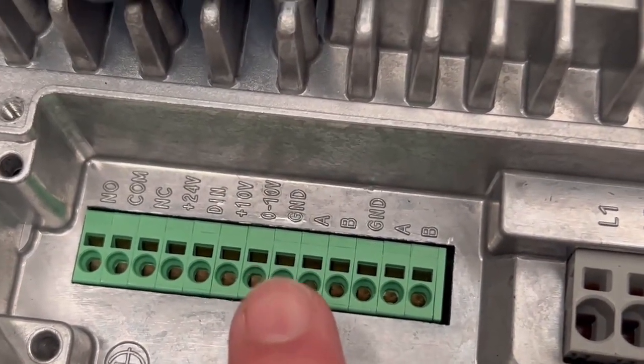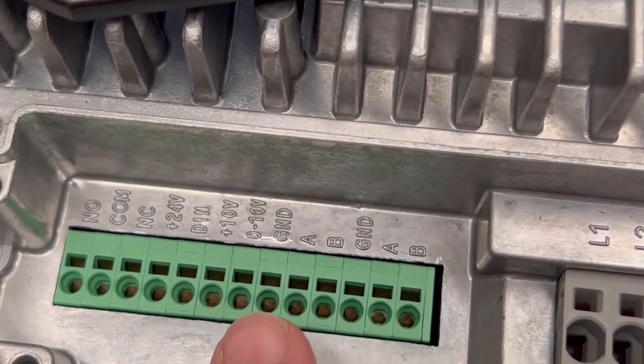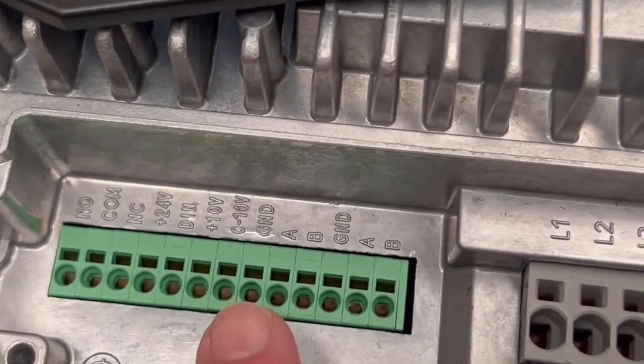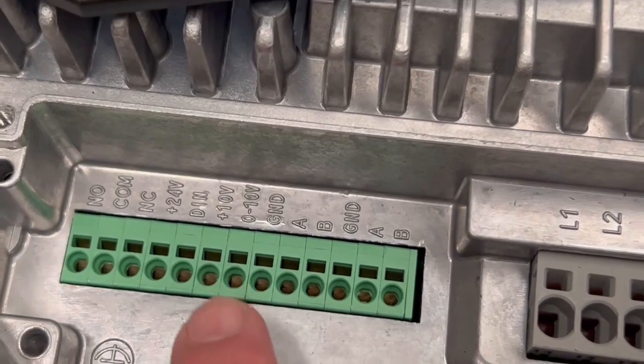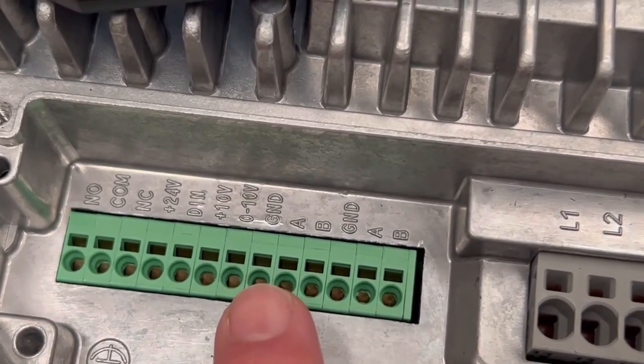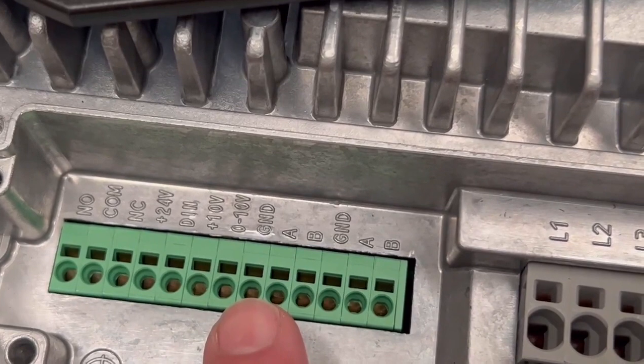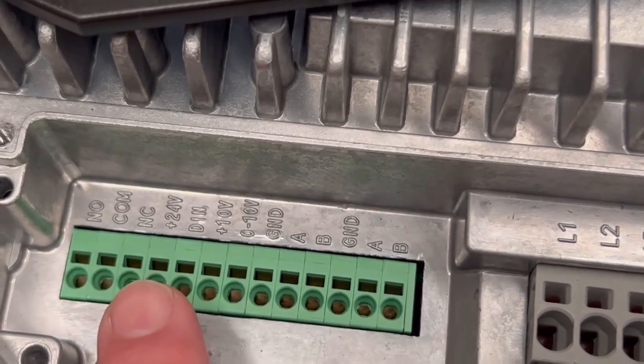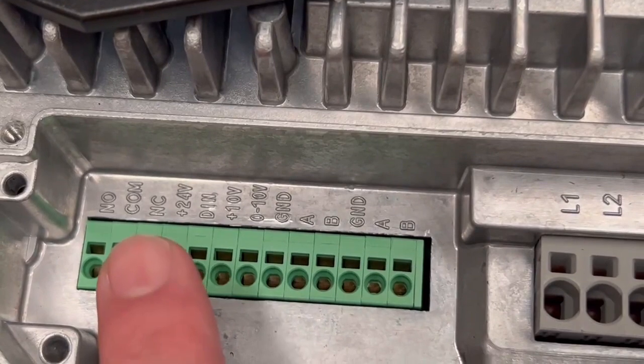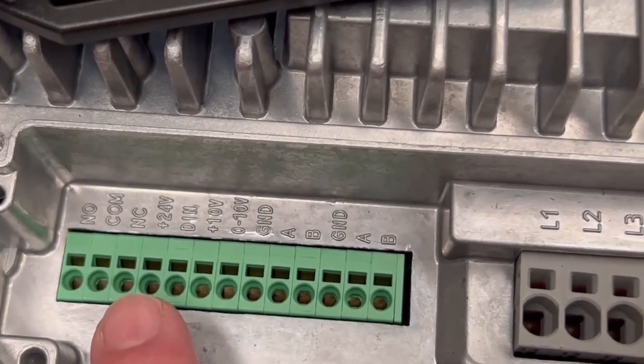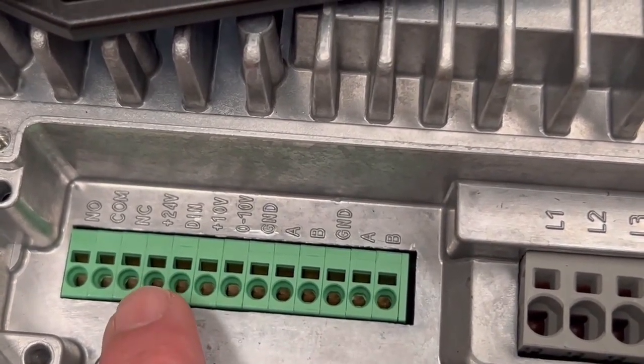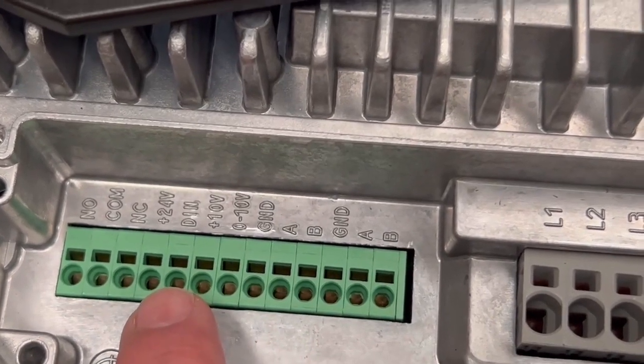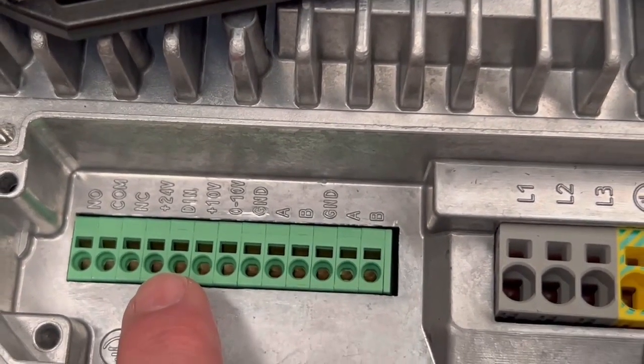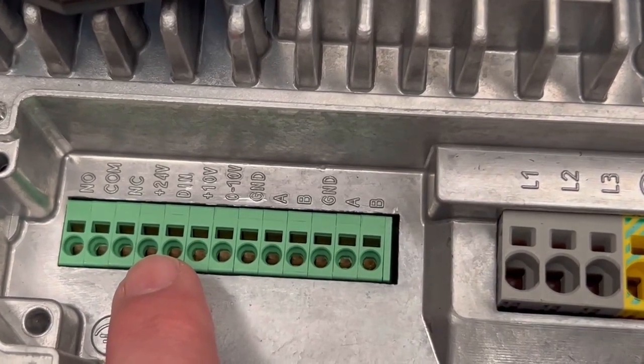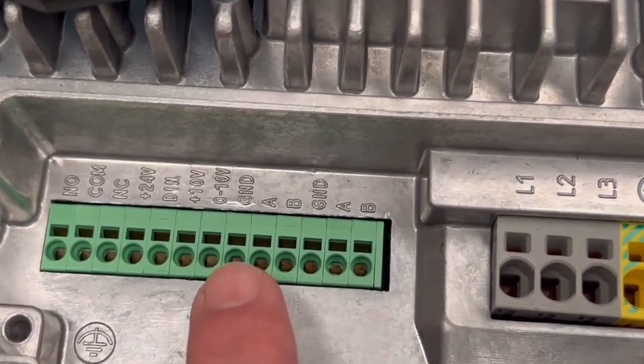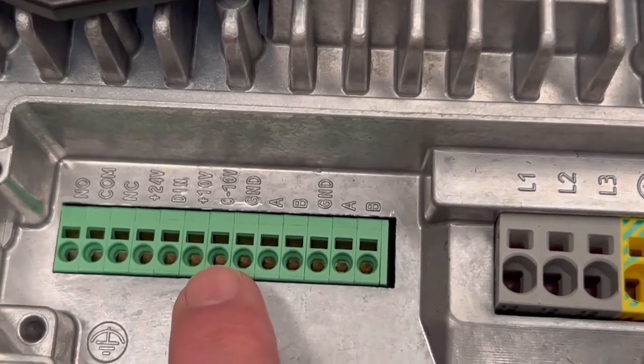When we're connecting to a PLC, we always have to make sure that the ground on here and the ground on our PLC is the same, because this is a reference. If we don't have that reference ground, the 0 to 10 volt does not know what it's referencing to, and you will not get an accurate result. A lot of these fans are all slightly different, so we'll talk about that in a moment, but most fans will require a run signal, and most commonly that run signal will come from the voltage, which is in this case the 24 volts, across to the digital input. So depending on how you're controlling this fan, you could close a relay to engage the fan, or you could keep that permanently closed and then control the fan using 0 to 10 volts only.